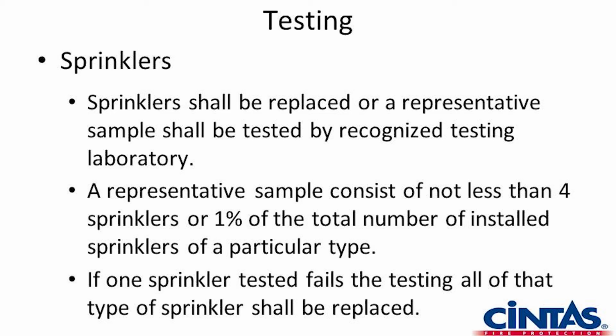instead of, in lieu of replacing all the sprinkler heads that are over 50 years old, we can send a sample, at minimum of 4 or 1% of the sprinkler heads installed, to UL. They will test them, and what they're testing them for is their reaction time. So standard response sprinkler, or if it's a quick response sprinkler, they're going to time how quickly it reacts. If it fails its inspection, every head that's in the area where that head originated from has to be replaced.